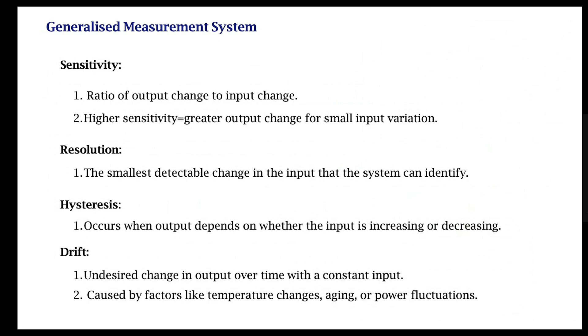Resolution is essentially the smallest detectable change in the input that the system can identify — the smallest value or change you can measure with confidence. If you increase the input and the output increases, then decrease the input and the output also decreases but not in the same manner, you have a situation called hysteresis, which is a manifestation of non-linearity.